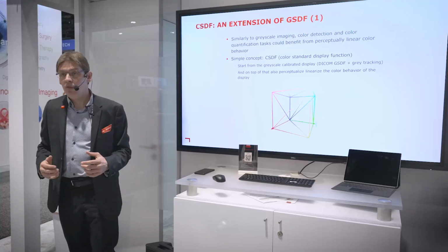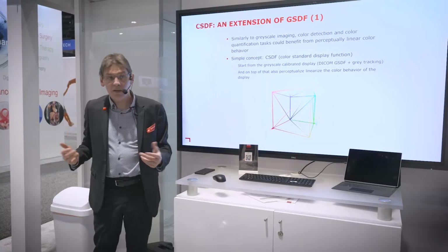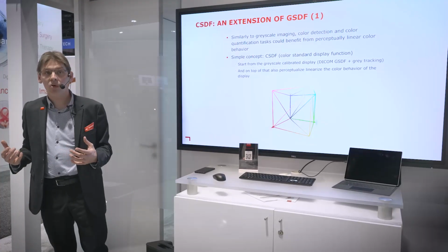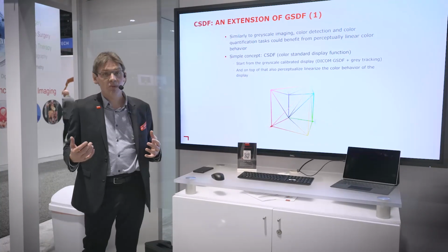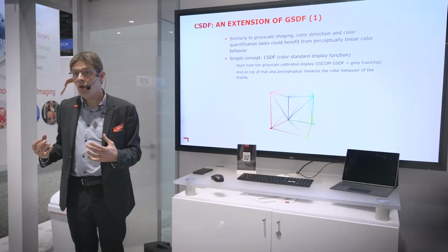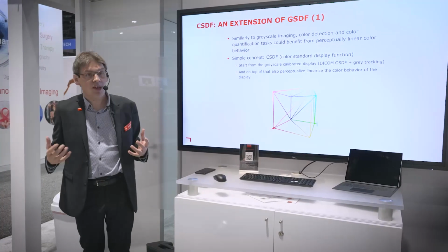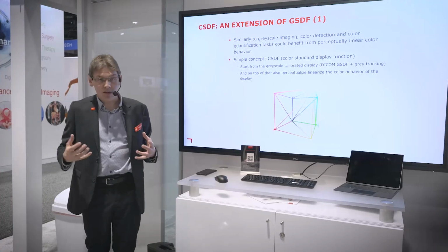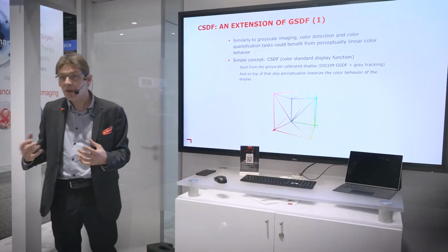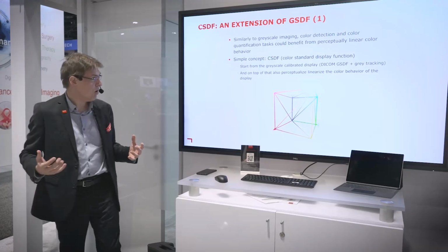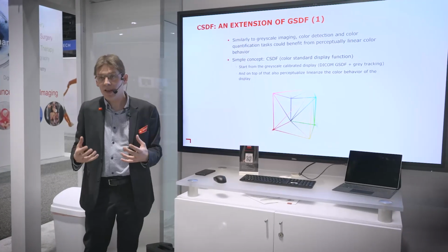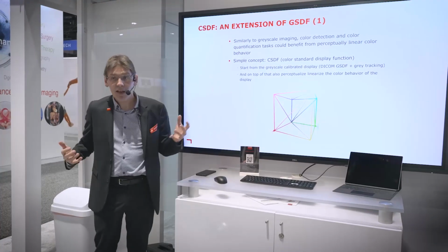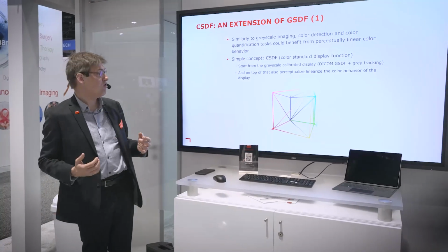What about color? Well, Barco is a leader in medical imaging. We're an innovator. So quite a few years ago, we realized that this was a problem, and we started working on extending the DICOM GSDF curves to also include color. So we proactively did research, we worked with key opinion leaders, we worked with regulators and so on, and we made a proposal to extend and include also color. So we called it the CSDF, the Color Standard Display Function.